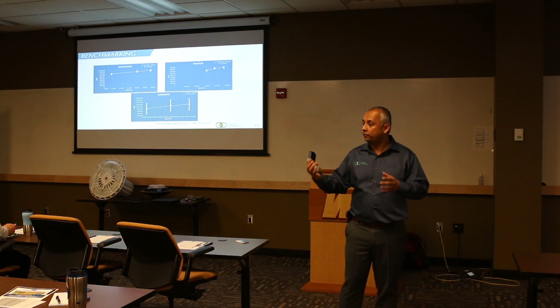So what did we learn from this? Come up with a facility baseline, a baseline that you will base your future energy savings from. Facility peaks and swings, once you do this exercise you will see those peaks and swings. Load factor, we talked about load factor. You take your total kilowatt hours, divide that by the maximum demand, and divide that by the hours you are running. That will give you the load factor, how loaded you're running in your plant.